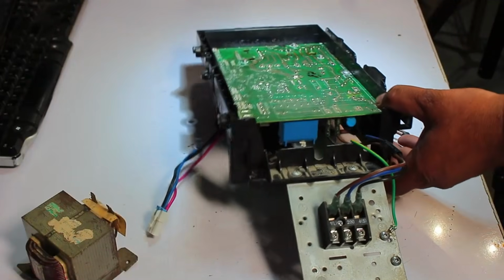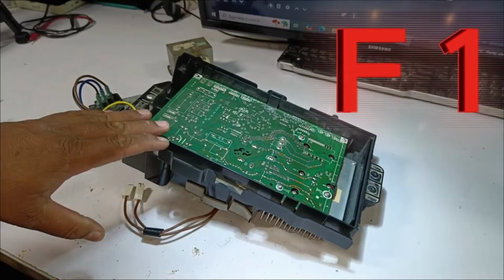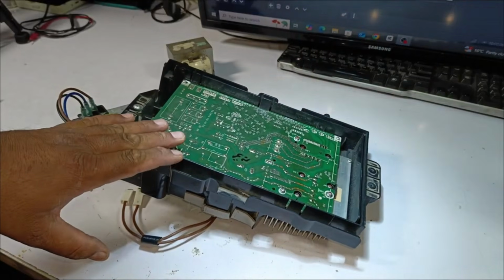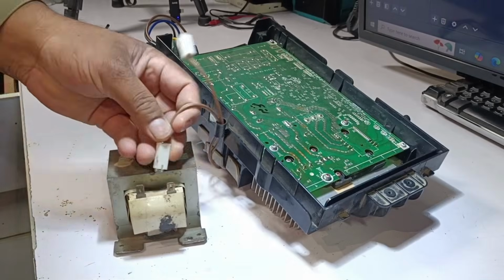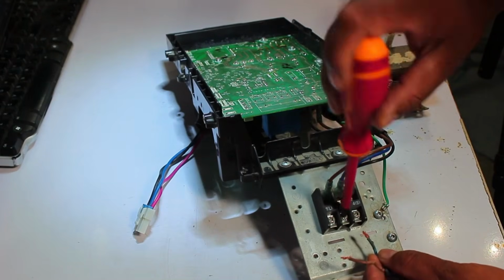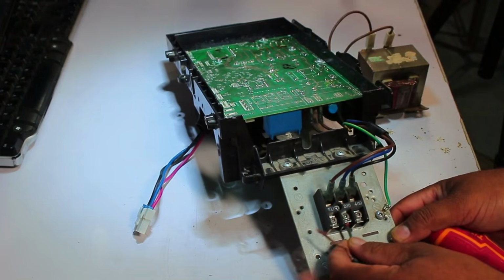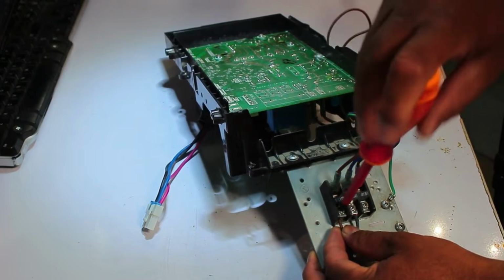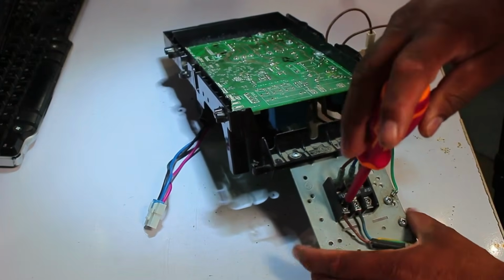The customer mentioned that this PCB has an F1 error. When I tested it, here's how I proceeded. First, I installed its reactor. Then, I connected the main supply, attaching the neutral wire to the neutral terminal and the line wire to the line terminal. We ensured all connections were proper.